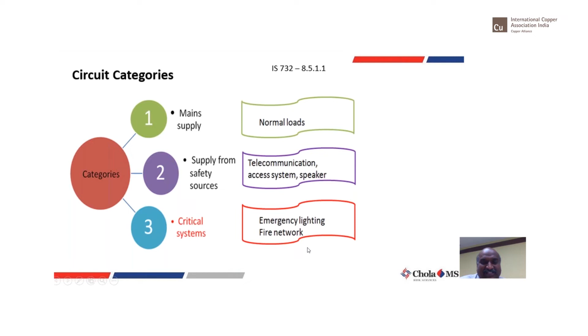They clearly say you should not mix one category with another - don't put everything together in one conduit and run it across. There are specific reasons for that. Category 3 circuits shall not be mixed with any other category in a conduit, because category 3 is connected to emergency lights and fire alarm networks. If you mix these circuits, there are chances of misalarm or false alarm, and interference which can create more trouble.